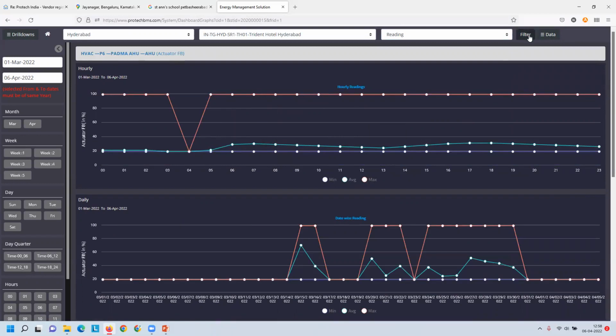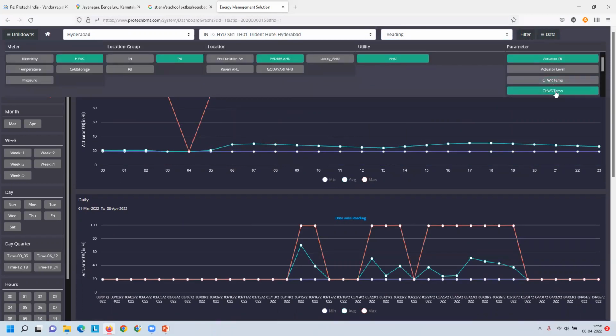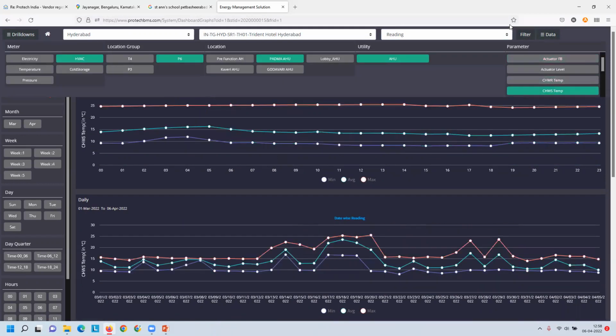I can select more parameters, such as what my chill water supply temperature is during this time period. You can see the average supply was maintained between 10 degrees and 25 degrees. The maximum average is 13.4. On a day-to-day basis it is 12 to 15, 12 to 15, and sometimes it increased to 16 to 22. So I need to understand why this is happening. I can select a particular date and get a complete data analysis for that. This is regarding the parameters.